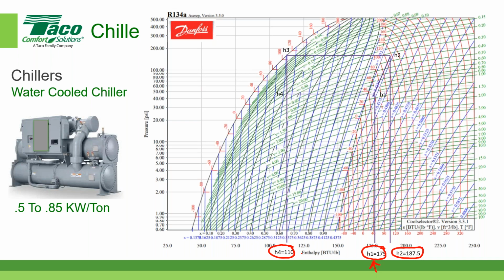And as it turns out, from this value here, H1 to H2, if you'll notice on the pressure enthalpy diagram, that starts right here and it ends over here. And the compression process, the process of the compressor, is called constant entropy, otherwise known as isentropic compression. And then these lines are horizontal lines. These are lines of constant pressure as they relate to temperature. So here is our pressure related to the evaporator temperature, and this is the pressure associated with the condenser, constant pressure.